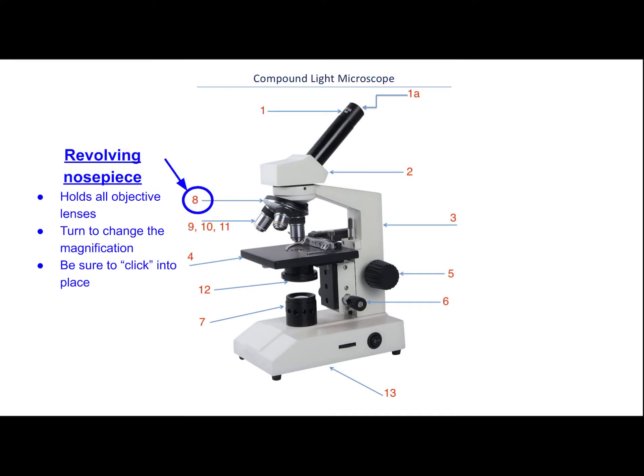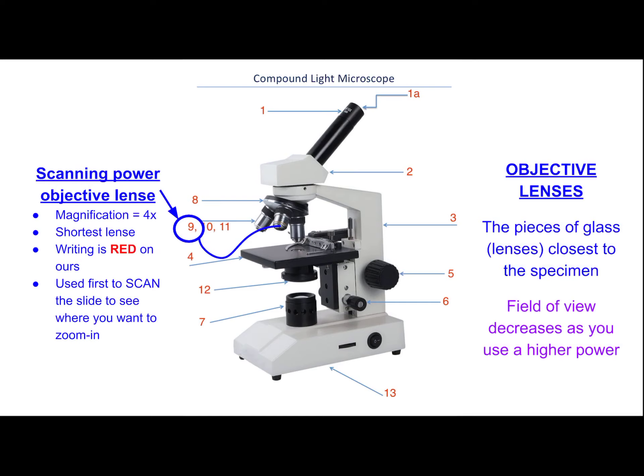There are three lenses on the revolving nosepiece. The first is the scanning power objective lens — it's the shortest. All three are objective lenses, meaning they are closest to the specimen. We start with the one that has the lowest magnification. On our scopes, the scanning lens has red writing. As its name suggests, you use it to scan the slide to find where you want to zoom in. The field of view decreases as you go to higher power, so use scanning power first, place your target in the center, then move to a higher power.